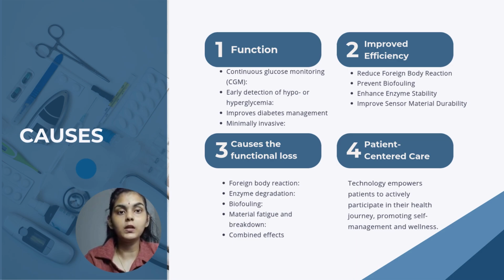Why the function loss is based on biofouling: accumulation of protein and cells on the sensor surface reduces sensitivity. Any inflammatory response, sensor drift, and loss of calibration over time lead to incorrect readings. Battery or molecule degradation: power and sensor material may wear out over a few weeks.